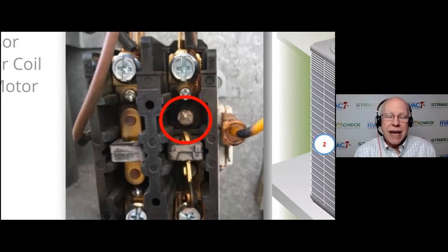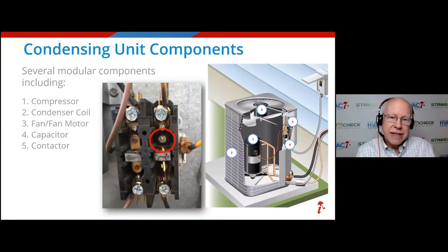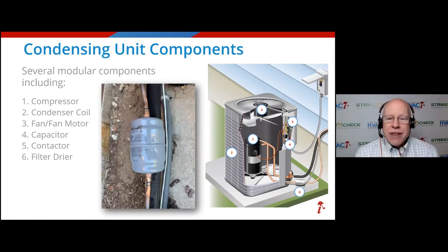Well, guess what happens? This thing cycles on and off dozens and dozens of times every day. Every time it makes contact and breaks contact, it arcs and sparks. And the contactors end up looking like this. That's not lightning damage. That's not surge damage. That's not water damage. That's wear and tear. And eventually it won't work at all. It's so pitted, they don't make good contact. You can almost get a brownout scenario and you can actually damage your system. I can't tell you how many times we've had systems fail and it's the contactor that has worn out. So again, just so you know what these components are, what they do and how they could play into a claim scenario. Now we're onto the filter dryer, which is even a less known item on HVAC systems.